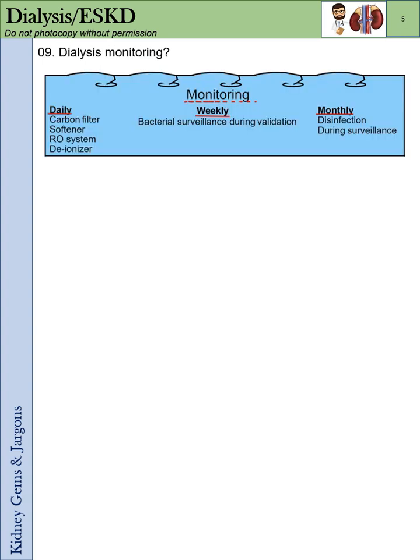Dialysis monitoring. You monitor daily: the carbon filter, the softener, the RO system, and the deionizer. Weekly, you perform bacterial surveillance. Monthly, you perform disinfection.